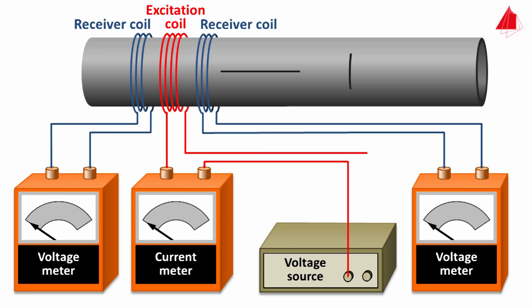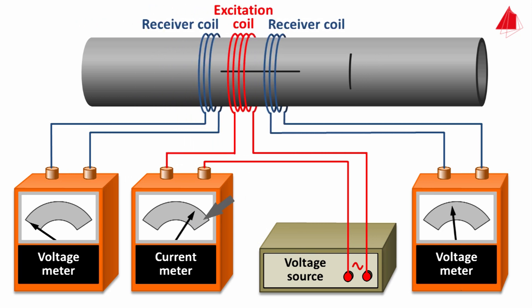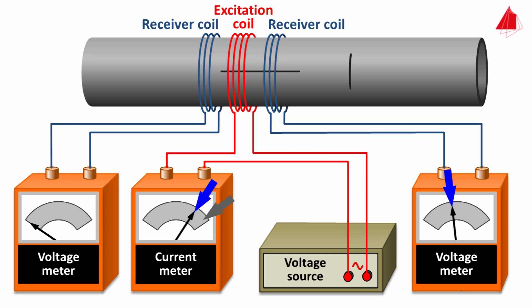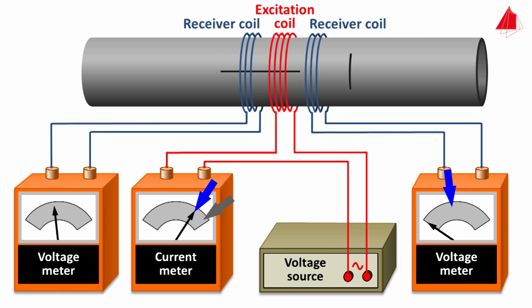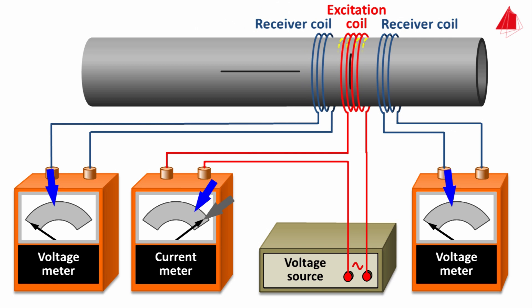The animation shows the physical background. Current consumption is high in the intact area due to undisturbed eddy current flow; because the eddy current's magnetic field doesn't flow through either receiver coil, virtually no voltage is measured on them. As soon as the excitation coil reaches the left end of the longitudinal saw cut, current consumption decreases because the eddy current now flows partly underneath the right receiver coil, inducing a voltage there. When the excitation coil reaches the right end of the longitudinal saw cut, the eddy current partially flows under the left receiver coil and induces a voltage there. Near the circumferential saw cut, the eddy current is undisturbed, its alternating magnetic field flows through neither receiver coil, and the voltage meters indicate almost nothing.